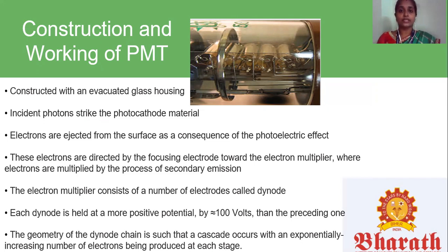A primary electron leaves the photocathode with the energy of the incoming photon, 3 eV for a blue photon, minus the work function of the photocathode. A small group of primary electrons is created by the arrival of a group of initial photons. The primary electrons move towards the first dynode because they are accelerated by the electric field. They each arrive with approximately 100 eV kinetic energy imparted by the potential difference.